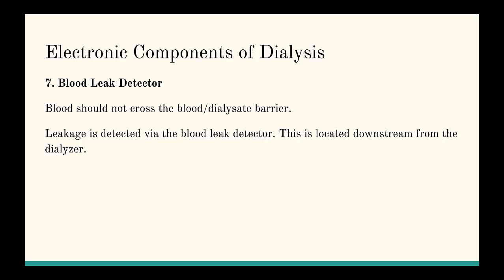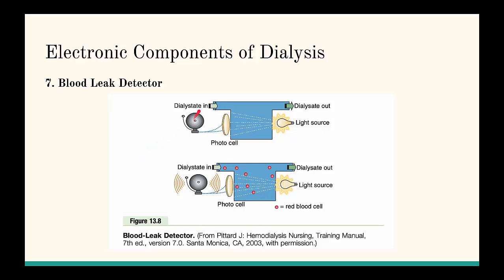Sometimes this membrane can be compromised, and when it's compromised, the blood might actually be going across into the dialysate. By blood I mean blood components, some of the components of the blood, such as red blood cells. If it does that, we also have to make sure that the procedure is stopped because blood should never cross the blood dialysate barrier, and we detect the leakage via the blood leak detector, and this is located downstream from the dialyzer, from the filter. As you can see, there is a good image here. We have the dialysate in, dialysate out. Sometimes we have red blood cells here, and the light source sends photons, and if the photocell detects an anomaly, there are things that are not supposed to be there, then the system is stopped.